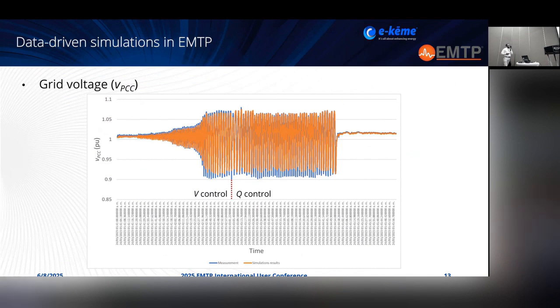Here in this figure, we can see the grid voltage. We compare the measurement and simulation results. As we can see, the simulated voltage is very similar to the grid voltage that we see in the measurements. But there is a notable difference in the minimum value that we got in simulation. This will be explained in the further slides. Practically, the plant was compensating reactive power, and that's why there was a minimum value different from the measured one.